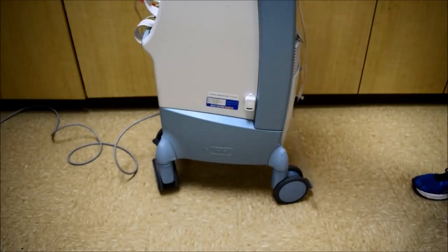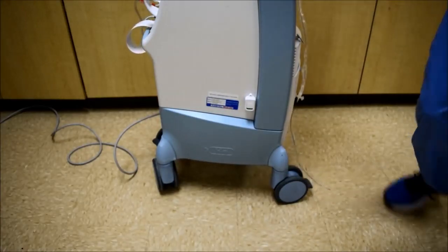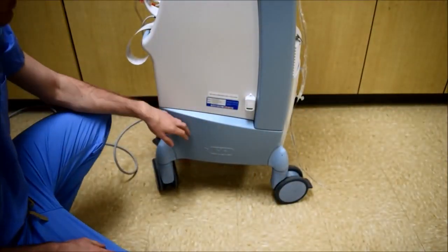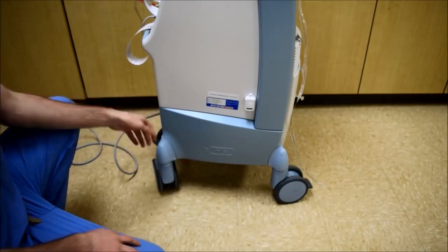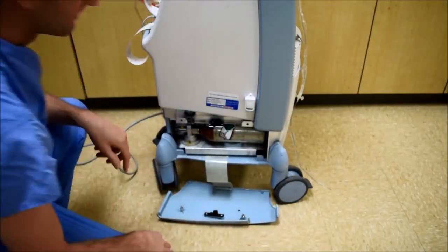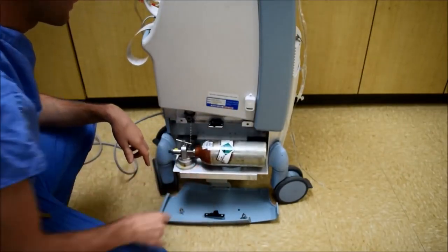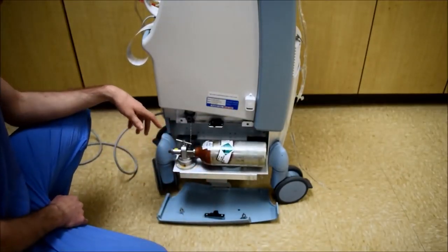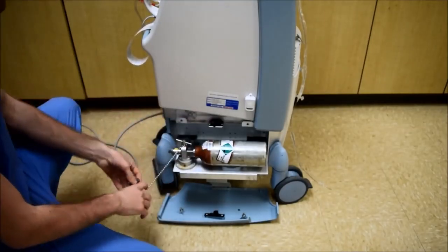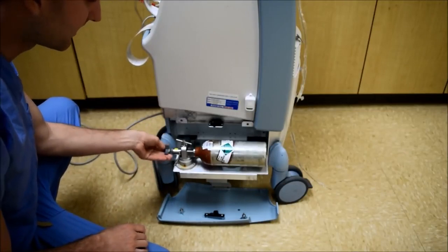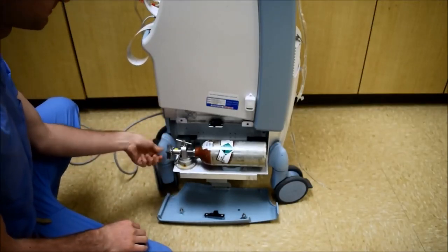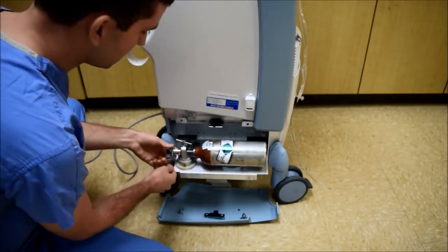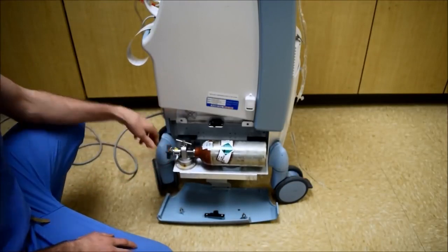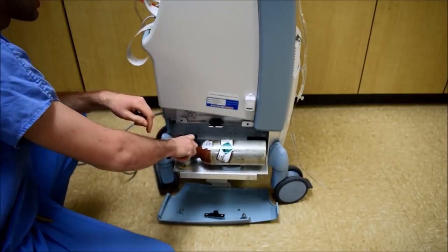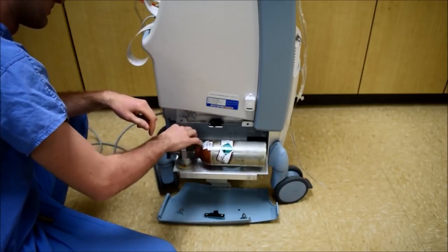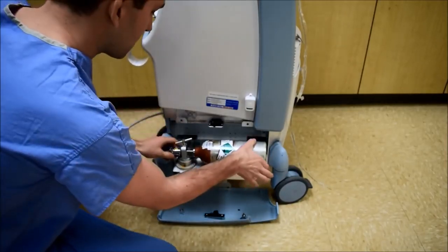To replace the helium tank, first shut off the balloon and come over to the left side panel here. On this lower panel, there'll be a helium tank here. Move the panel. Here's the tank. Slide it out. Now first we'll have to make sure that the helium is shut off. In order to do this, take this key, slide it on the end here, and tighten it all the way. Once it's tight all the way, then we can remove the helium tank. Unscrew this on the top and remove the tank.